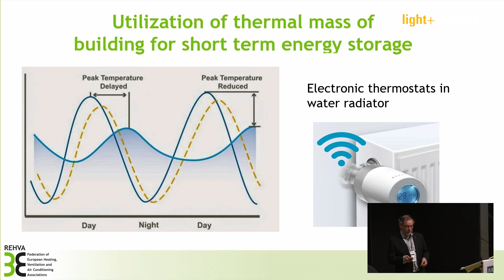And if we have a space control principle, we also prevent the trend that some areas are overheating or overcooling, like what could happen with a centralized system. So a big advantage of utilizing the thermal mass is that we have individual controllers in each space. There are already electronic thermostats on the market that can be controlled from the cloud. So they are IoT systems that, based on the price, can reduce or increase heating power in the space. There are some small motor valves that are used. So it means that we are charging and discharging the thermal mass in the building based on the price. That's the main principle of that.